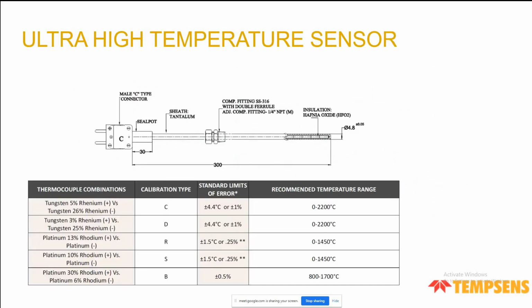We also do a lot of ultra high temperature sensors. The B-type thermocouple can go up to a maximum of 1700 degrees centigrade. But when the application requires more than 1700 degrees centigrade, we measure it with a type C or type D thermocouple. These can go up to 2200 degrees centigrade in non-oxidizing atmospheres, either reducing or vacuum. So we can measure temperature up to 2000 degrees centigrade with type C or type D thermocouple. The outside tube can be tantalum or...